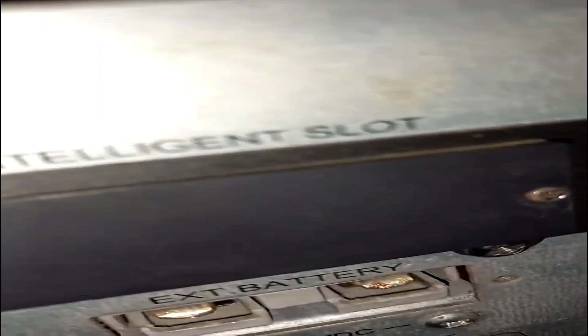First of all, you open the case and switch on the power on the input side. When switched on, you first check the DC power, that means the back side of the UPS. See here, this is the DC power connector. Check with a multimeter how much DC voltage is coming from the inside or charger. If it shows 109 DC volts, then it is okay.